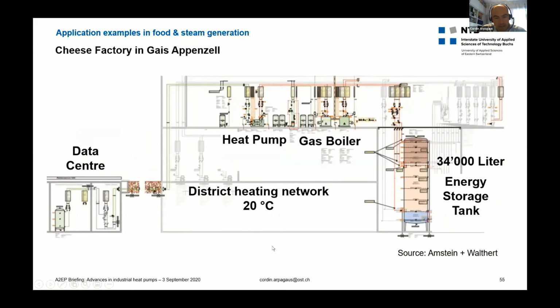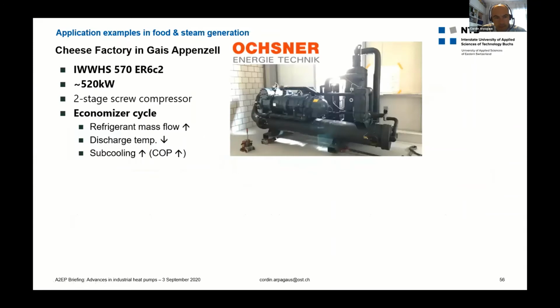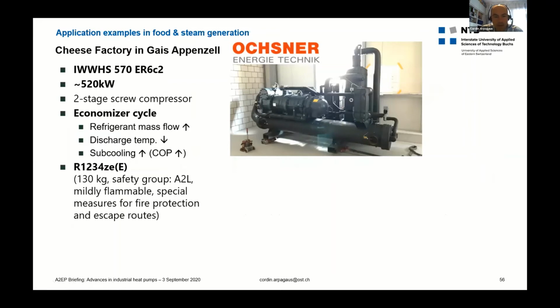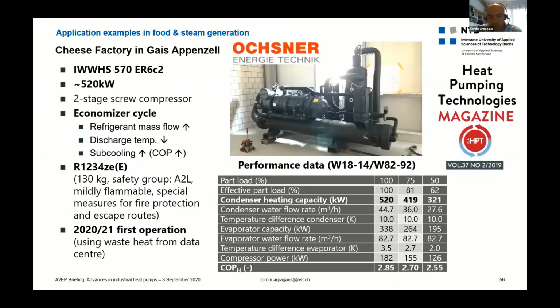Here is another graph showing how they installed it in their company. The heat pump used is an Ochsner heat pump, shown here with 520 kilowatts. It uses an economizer cycle and a two-stage screw compressor. This heat pump cycle is beneficial for high temperature lifts, and it uses a hydrofluoroolefin refrigerant with a low global warming potential. It's going into operation very soon, or is already in operation.